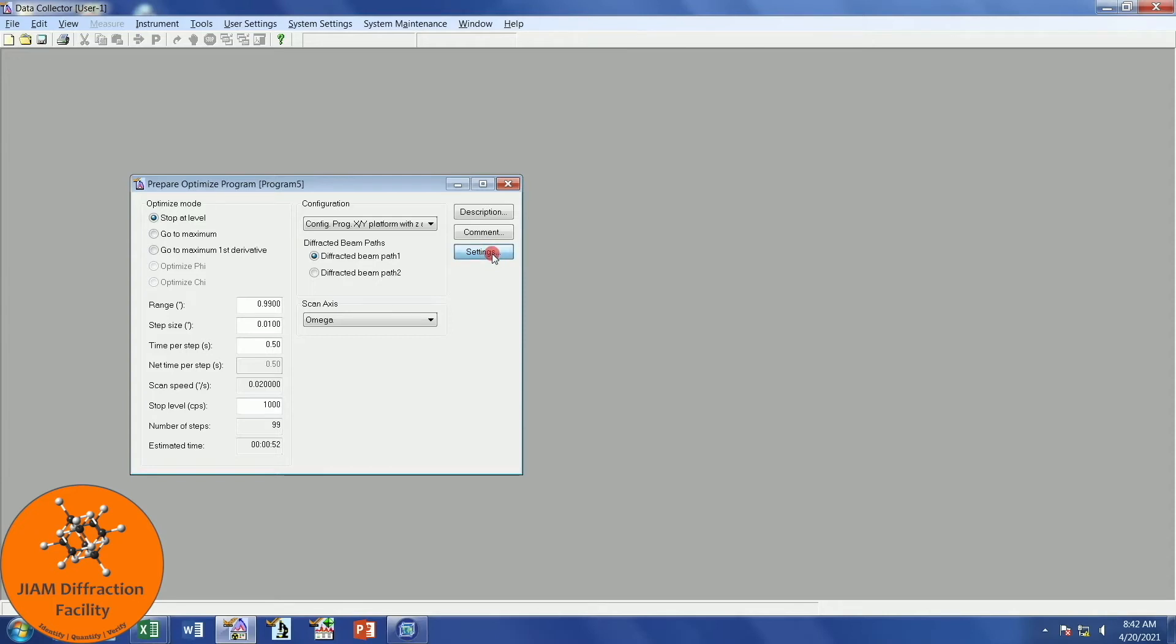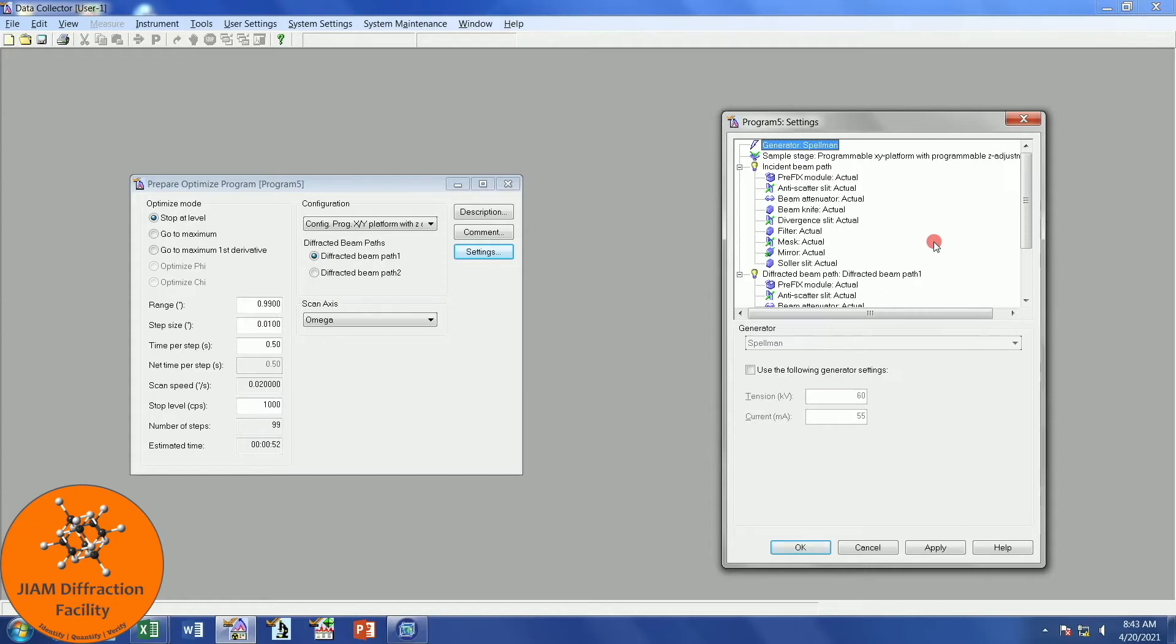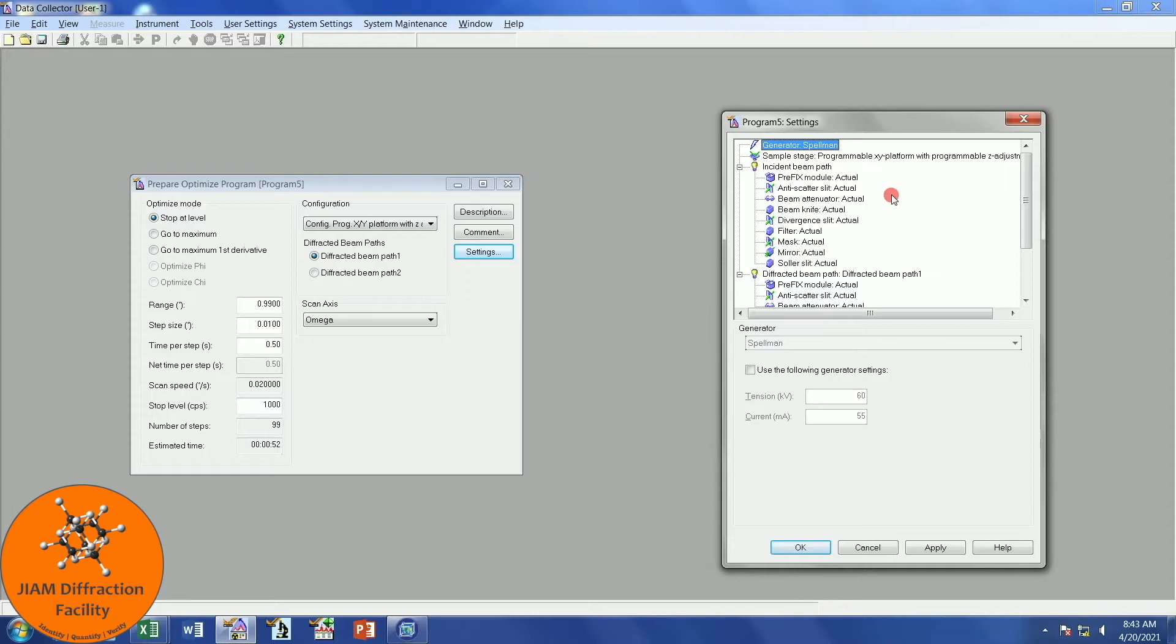Now we can go into the settings, and we have some options here. What you can do is insert your hardware settings here that you will use for alignment. And if you do that, once your program runs, it will check your settings and make sure that they are all correct. If not, it will warn you so that you can find a way to correct your mistake and move forward. However, different measurement techniques will require different prefix modules and optics. As such, I'm not going to set these here. You should be able to see that information in our measurement tutorial videos. You'll know what to use for alignment based off of those.